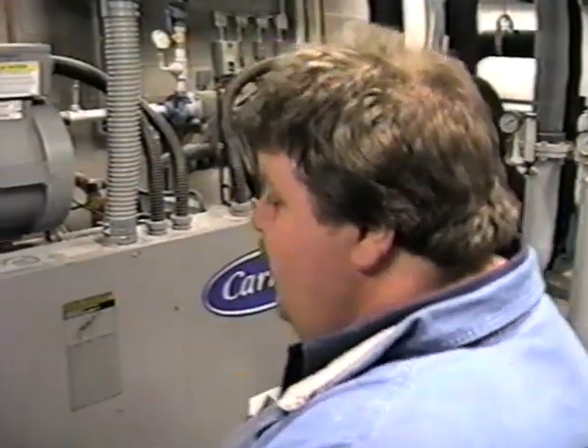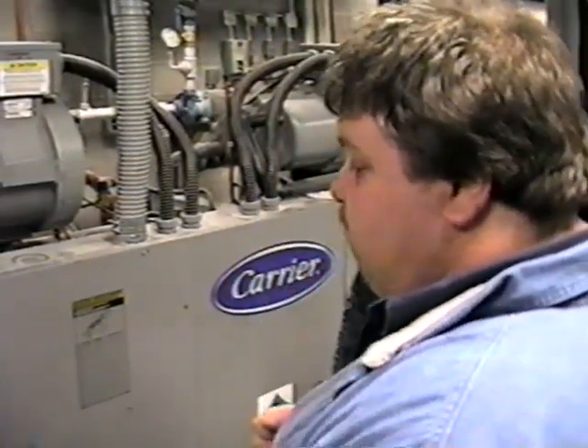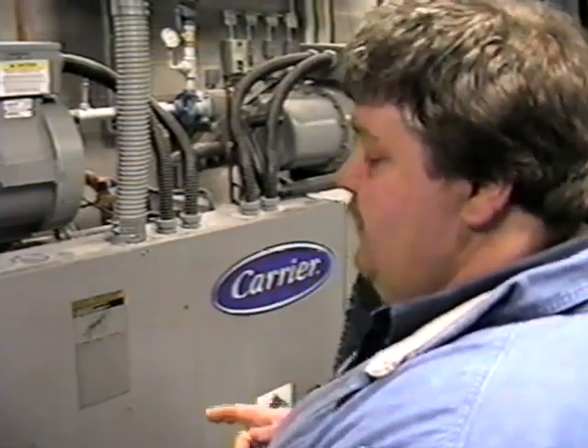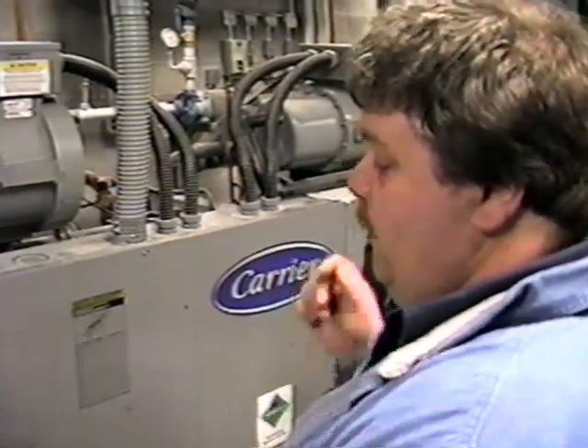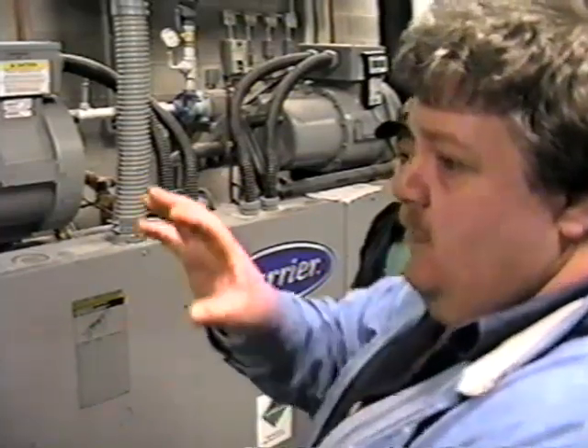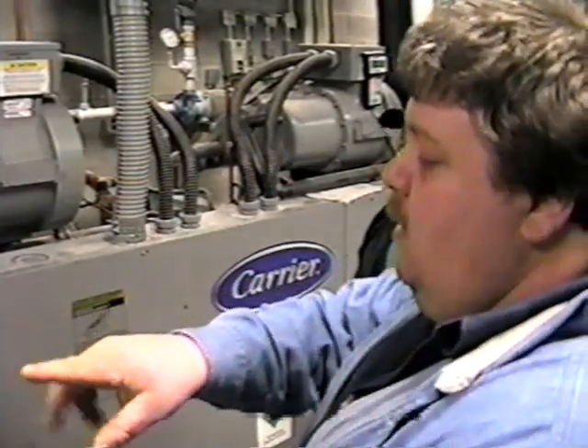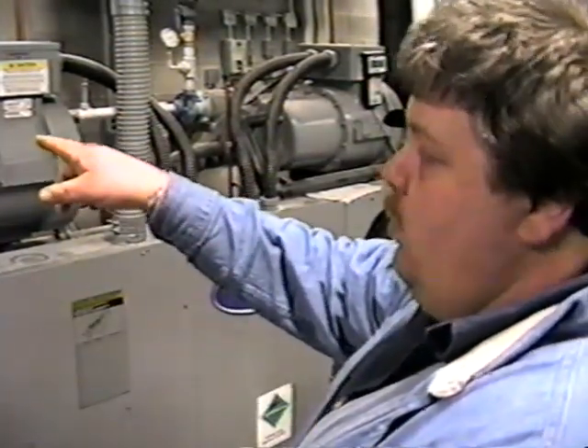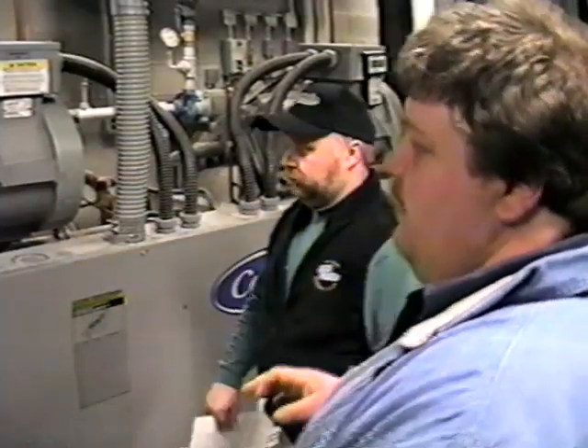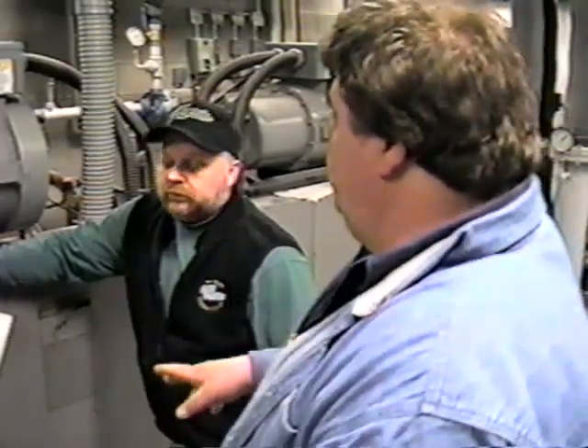The only other thing, really, is that if you have a refrigerant leak in here, we have the Sherlock monitor over here. That's sending a signal to our panel also, and it's interlocked with the chiller start logic. If the chiller's running and we get an alarm from the panel, the chiller's going to be cycled off and locked off until the alarm is cleared.